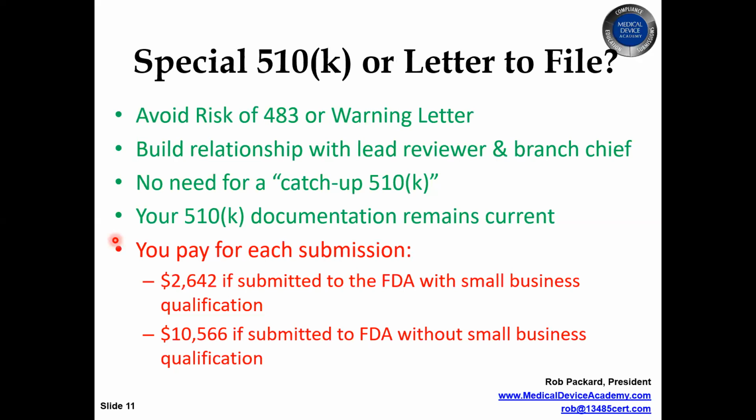And really, you should be doing catch-ups every so many years because all these little minor modifications add up pretty quickly. You also would be able to keep your 510K documentation current. I see companies that are 5, 6, 7 years old on their 510K. They have a lot of trouble updating it. They don't understand why their 510K that they submitted, they can't use any of that documentation because it doesn't meet any of the current guidance requirements.